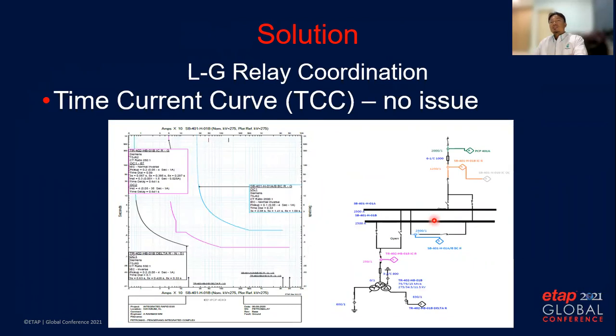The EPCC contractor for this project had recommended enabling earth fault protection as a backup to differential protection. They proposed both directional and non-directional earth fault relays. If we look at the TCC, there is no issue on the coordination — everything looks good.